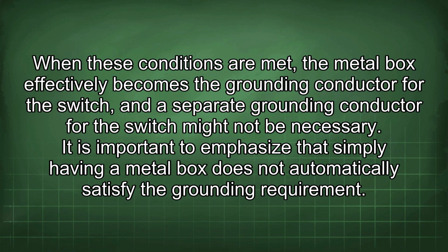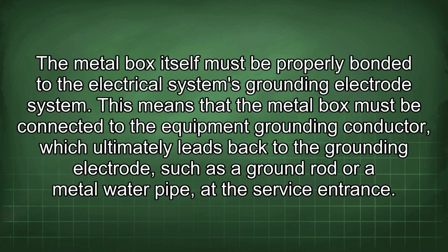It is important to emphasize that simply having a metal box does not automatically satisfy the grounding requirement. The metal box itself must be properly bonded to the electrical system's grounding electrode system. This means that the metal box must be connected to the equipment grounding conductor, which ultimately leads back to the grounding electrode, such as a ground rod or a metal water pipe, at the service entrance.